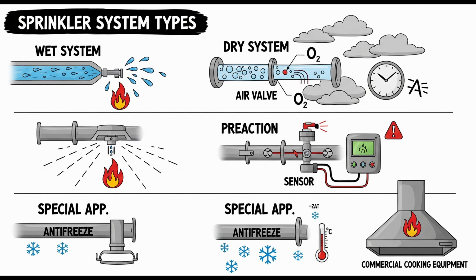Makes sense. The automatic water control valve for these systems, the pre-action or deluge valve itself, must have a manual means of operation, like a handle, pull station, something mechanical. So you can trip the system manually if the automatic detection fails or isn't fast enough? Yes, a crucial backup.